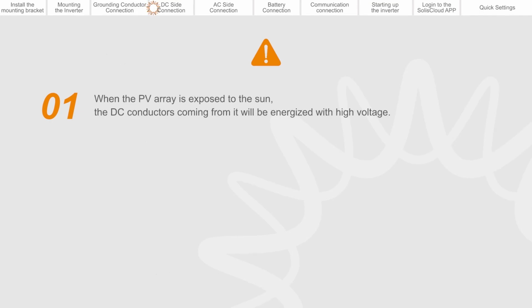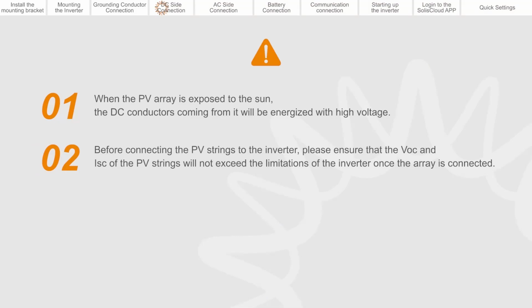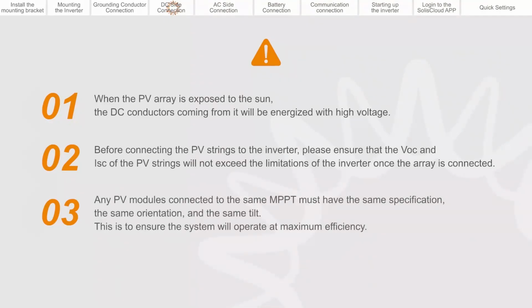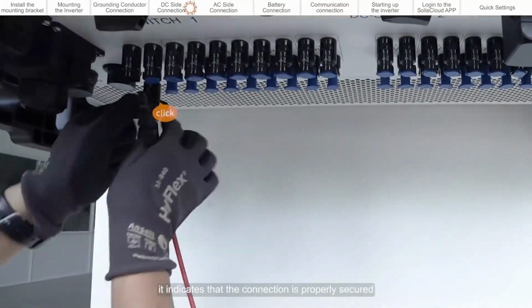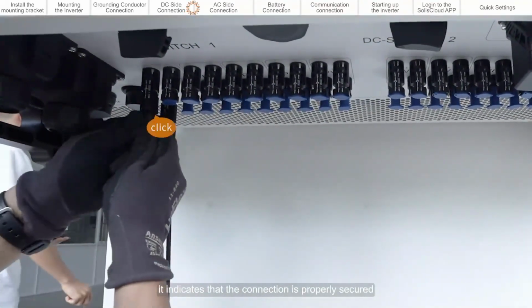When the PV array is exposed to the sun, the DC conductors coming from it will be energized with high voltage. Before connecting the PV strings to the inverter, please ensure that the VOC and ISC of the PV strings will not exceed the limitations of the inverter once the array is connected. Any PV modules connected to the same MPPT must have the same specification, the same orientation, and the same tilt. This is to ensure the system will operate at maximum efficiency. When you hear a click sound, it indicates that the connection is properly secured.